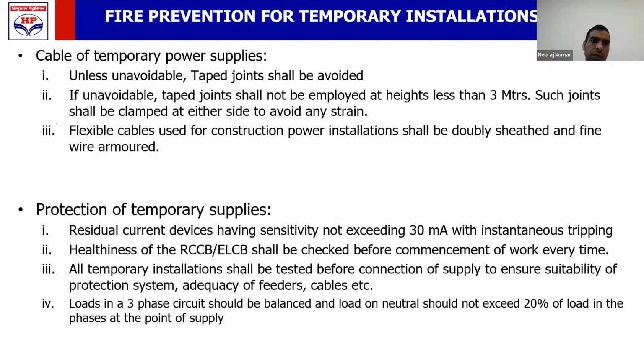For that also, this standard gives us the way. The standard tells us that when you construct your plant, you make provisions for temporary power supply. That temporary power supply is available at every 50 meters. Those provisions shall be both 3-phase type and single-phase type, flame-proof type. So whenever you need a temporary supply, you put your main switching station taking power from this permanent arrangement made available in the plant for temporary purpose.